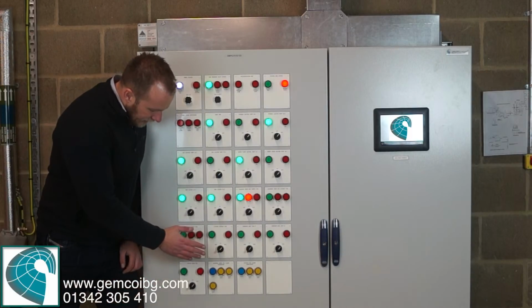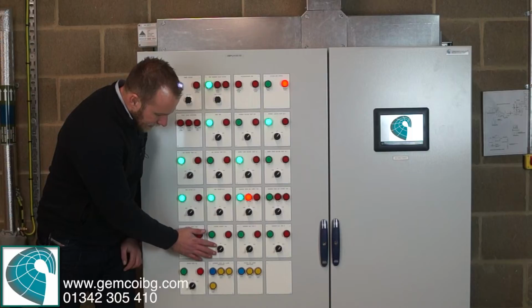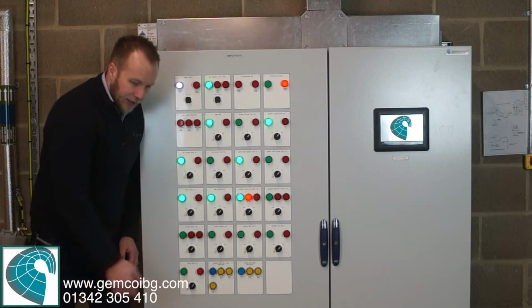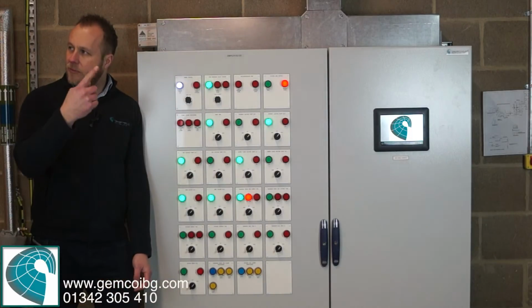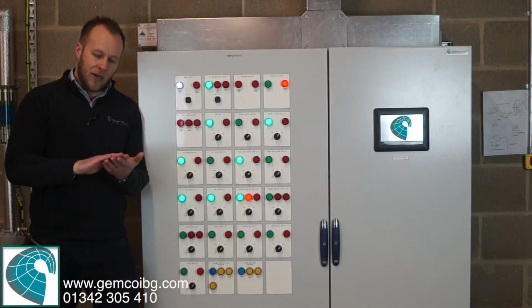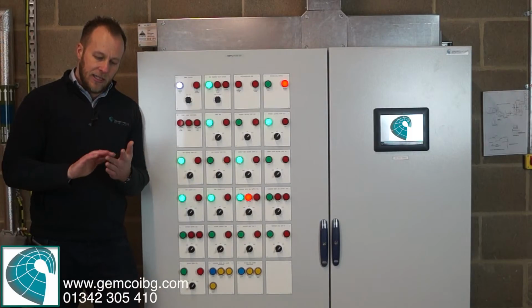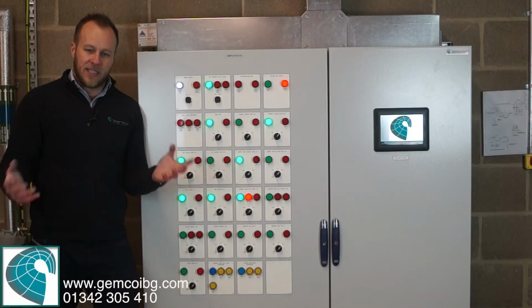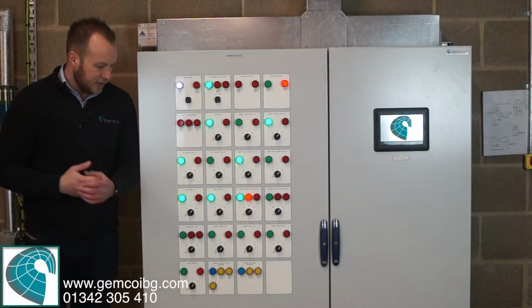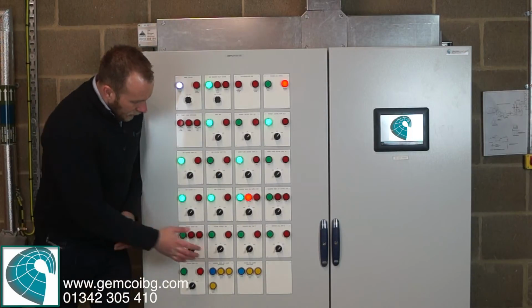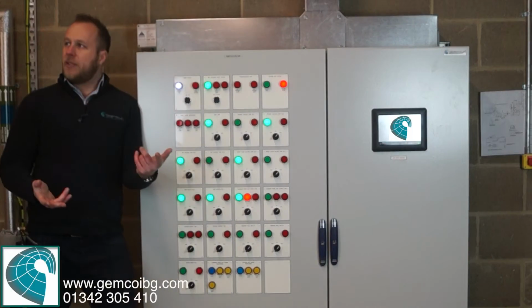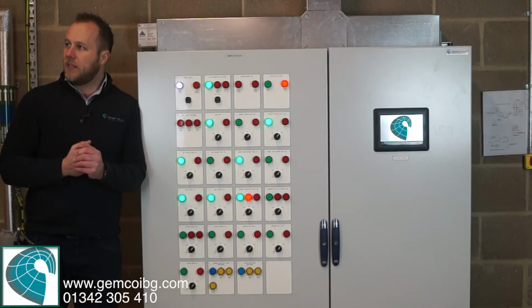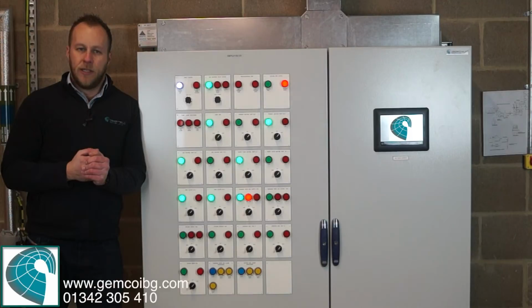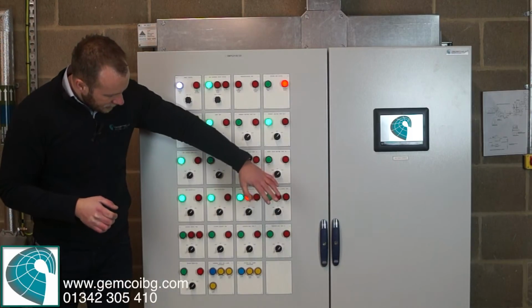Same with the kitchen. The kitchen's fan is enabled from here, although you need to initiate it from the key switch upstairs. And we need to just bottom out that whole sequence with the gas proving, because if the gas goes into alarm, then whoever's in the kitchen is going to get a bit annoyed. Once the fans are enabled, they've got heating valves, so they just temper the air, maintain 21 degrees. That's the set point. You've got three on the changing room.